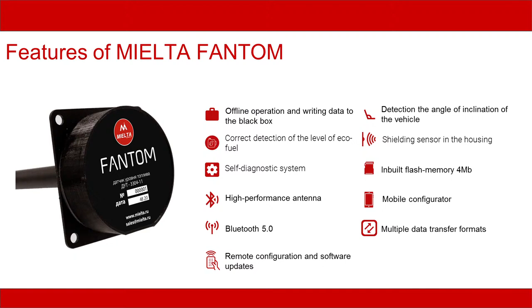Let's start with the most important thing, in our opinion: measurement. The principle of level measurement is classic, it's linear - a capacitor in the form of a pipe and an electrode immersed in the fuel. The measured value is the condenser capacity.